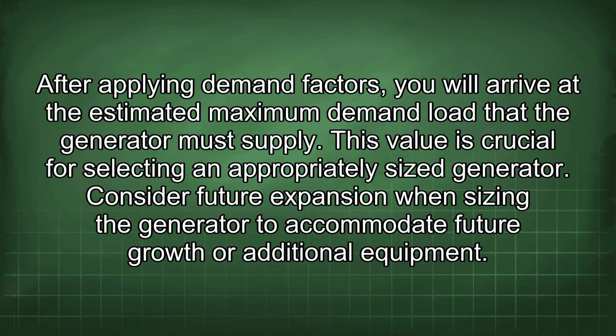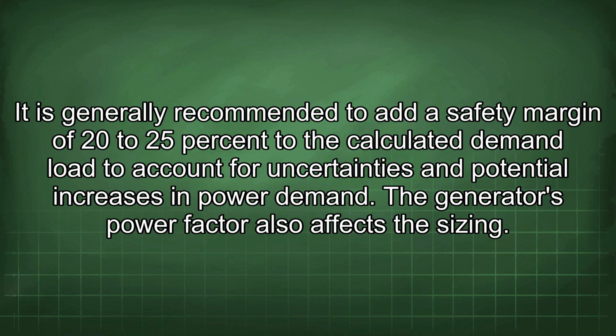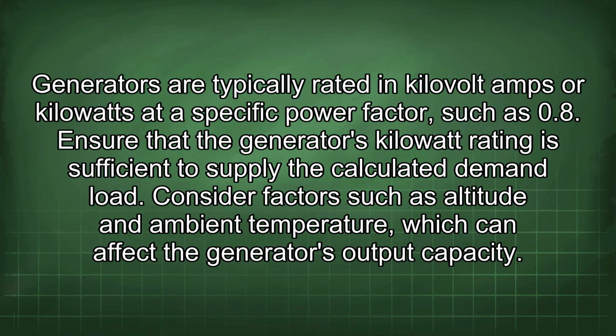Consider future expansion when sizing the generator to accommodate future growth or additional equipment. It is generally recommended to add a safety margin of 20 to 25% to the calculated demand load to account for uncertainties and potential increases in power demand. The generator's power factor also affects the sizing. Generators are typically rated in kilovolt amps or kilowatts at a specific power factor, such as 0.8. Ensure that the generator's kilowatt rating is sufficient to supply the calculated demand load.